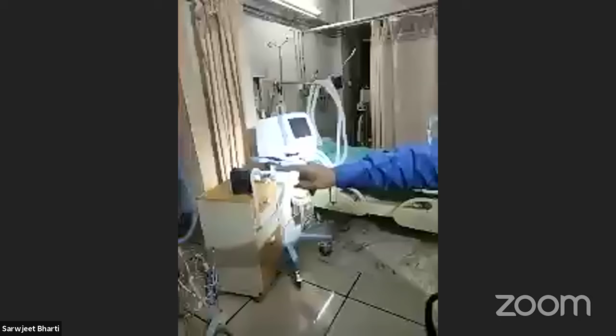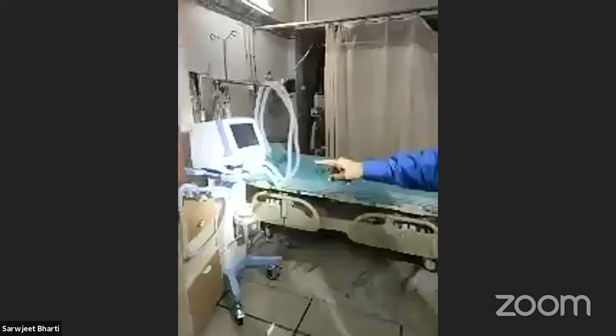Then we have the expiratory port. At an expiratory port, you must invariably put a HEPA filter or a viral filter and then connect it to a mechanical PEEP valve. This mechanical PEEP valve is absolutely essential, whether you use this bubble helmet with CPAP, with high flow, with pressure support ventilation, or with the BiPAP machine. Because this is one which acts as an anti-suffocating valve. If you don't do this with only one port, we'll have suffocation. So we have added this, and we reduce the PEEP level to the patient's comfort, and also to reduce the suffocation to the patient. That is one aspect of it. Whenever we have this HEPA filter or viral filter at the expiratory port of these bubble helmets, it reduces the viral load in the ICU drastically. So this is a great advantage and benefit to the healthcare professionals who are working in the ICU.